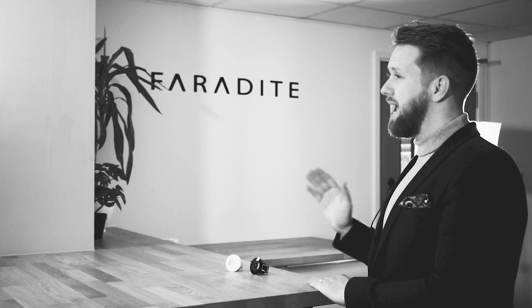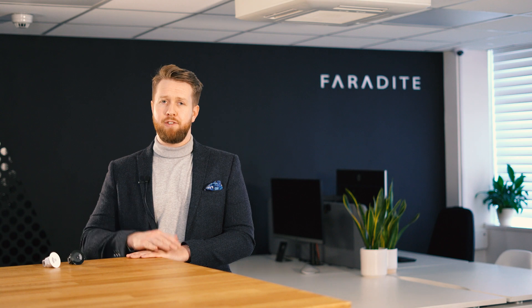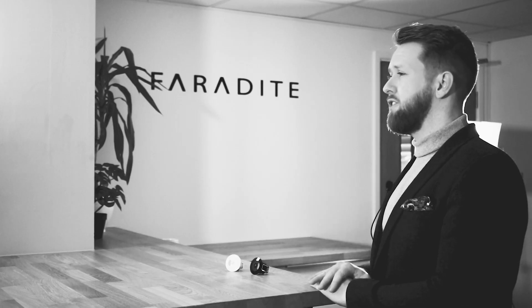We've also included some really nice advanced push button inputs. This means you can interact with the motion sensor in the room by using a push button. For example, in a meeting room in an office the motion sensor may bring on the lights for five minutes should a member of staff walk into the room. When they leave, after the timeout the lights will turn off. However, in this same room, if staff are going to have a meeting and they press the switch, this can extend the motion sensor's lighting timeout as well as turn the HVAC on.